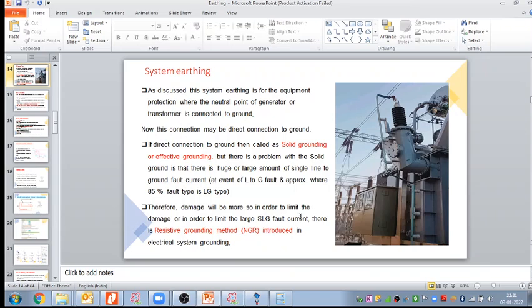So in order to limit the damage, or in order to limit the large single line to ground fault current, the resistive grounding method, NGR, was introduced. In electrical system grounding, we also use this NGR. The second type of grounding: first is solid grounding, whose drawback is a large line to ground fault current. The next grounding introduced is the NGR. In that, the NGR will limit the fault current.